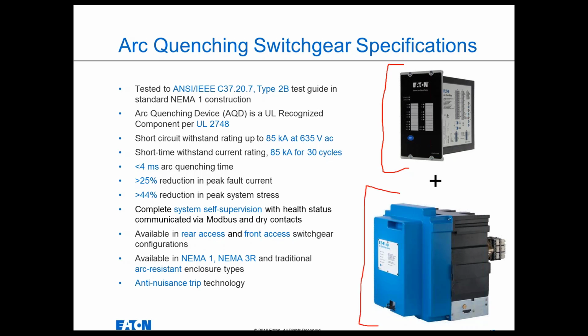And this is what we spent the last 6 years actually developing: this arc quenching device. As you can see, it kind of looks like a draw out breaker. There are line side finger clusters. It's actually the same form factor as an Eaton Magnum DS breaker, so it can be withdrawn from the switchgear if it needs to be replaced or serviced. But internally, it has absolutely nothing in common with a circuit breaker, but it does fit in a circuit breaker cell.